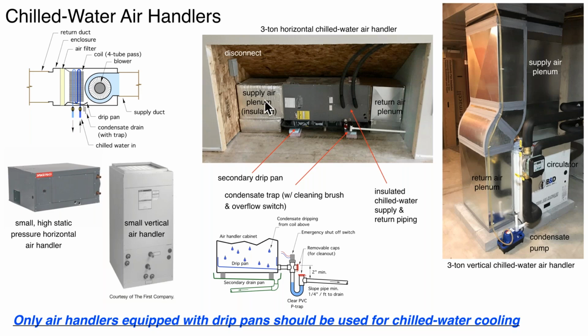Here's the return air and supply air plenum. Here's a disconnect. Here are the two 3/4 inch pre-insulated PEX lines that go to the coil. And down here you see the trap. The trap is needed, especially if you're going to take this condensate to any kind of DWV piping system. You don't want any type of sewer gas coming back out, and that piping needs to be pitched. Sometimes this runs outside. Sometimes it runs to a vent pipe in a system. Try to avoid it going directly into soil pipes and so forth.